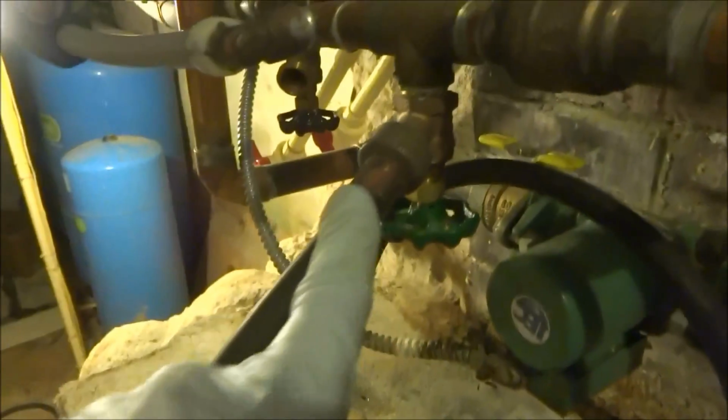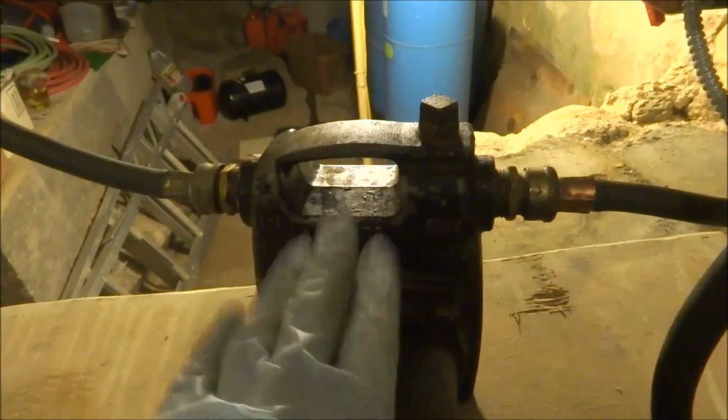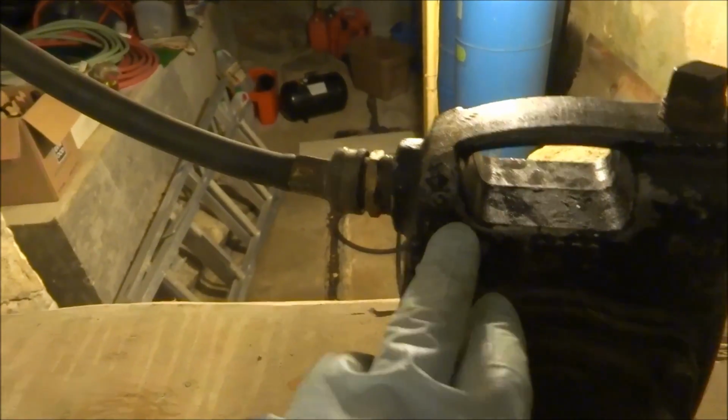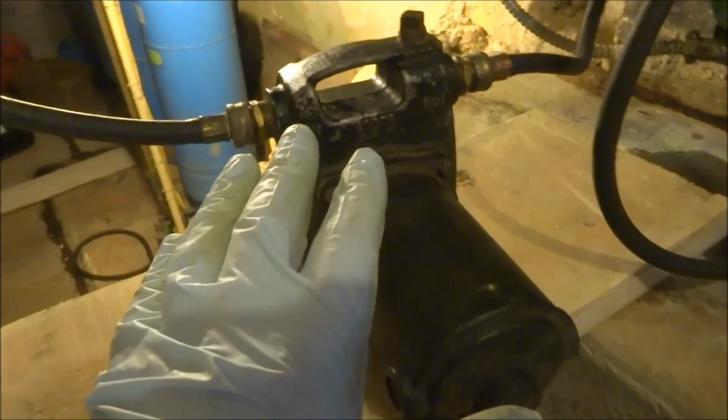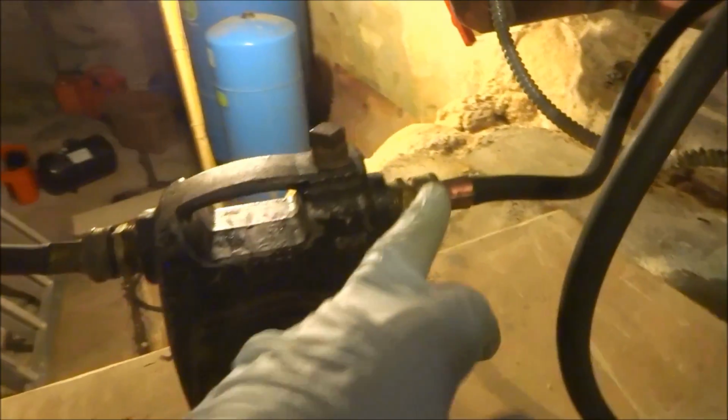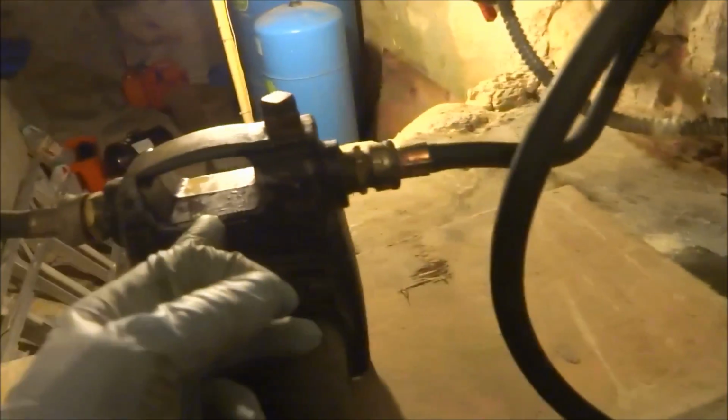Alright, so I'm going to be draining this one here. I'm going to push it through the pump to prime this pump because it needs antifreeze for it to work. And then it's going to dump into the bucket here. This way it'll be primed, ready to go. What we're going to need to do is go from here into the boiler for the pump, and then drain into this bucket and suck out of this bucket to purge it. But let me just open that for now.